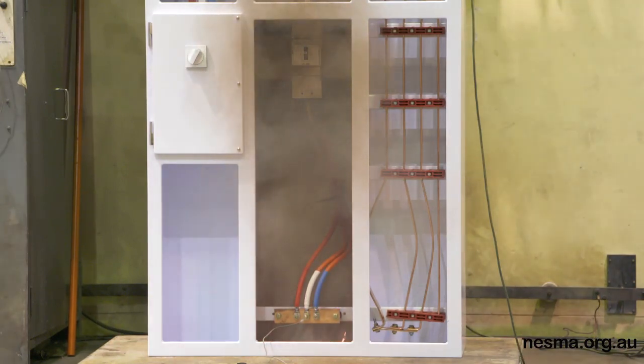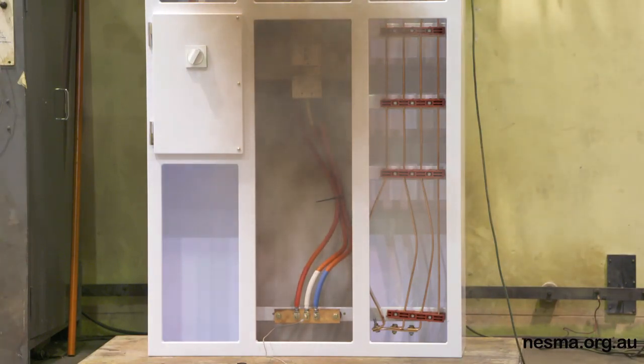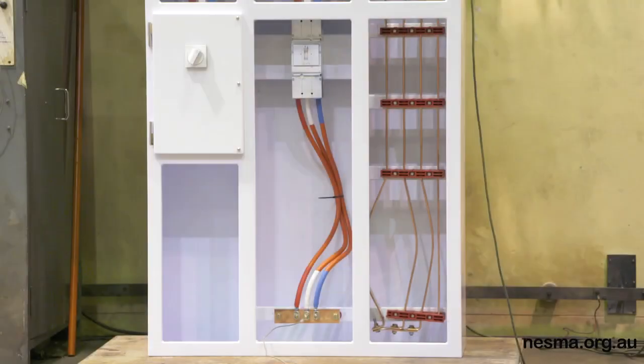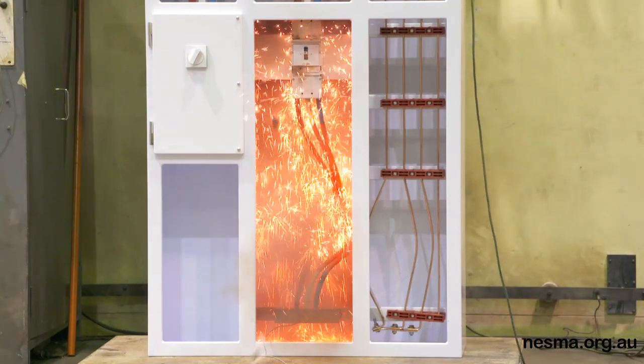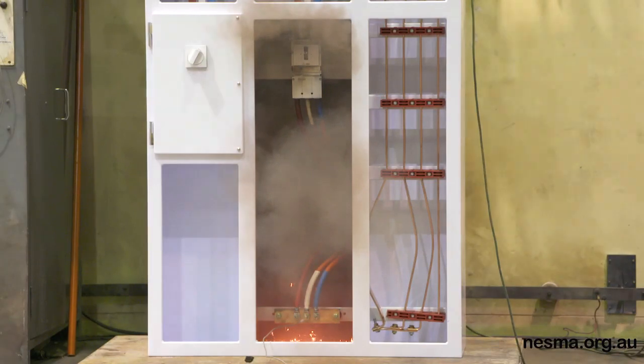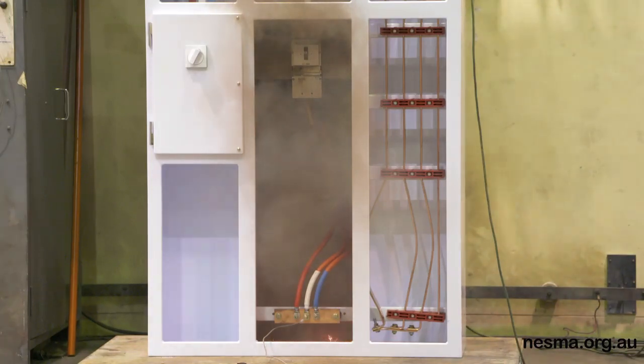You've got a serious fault level there, and when the contacts start lifting, because of the circuit breaker starting to operate, you are getting arcing at that main contact zone. The secret of the manufacturer to have a breaker that can handle the high fault levels is to ensure that arcing gets away from the contact zone as fast as possible, and then it is put into the splitter plates and then expelled from the circuit breaker housing. If you kept that arcing and that pressurization inside the molded case breaker, it would just shatter and fracture the housing of the breaker. It wouldn't be able to withstand that fault level.